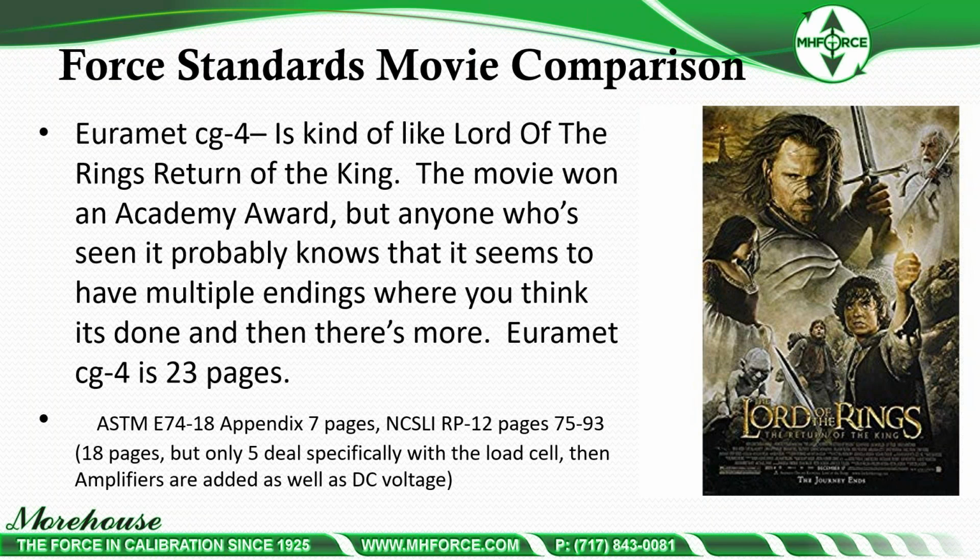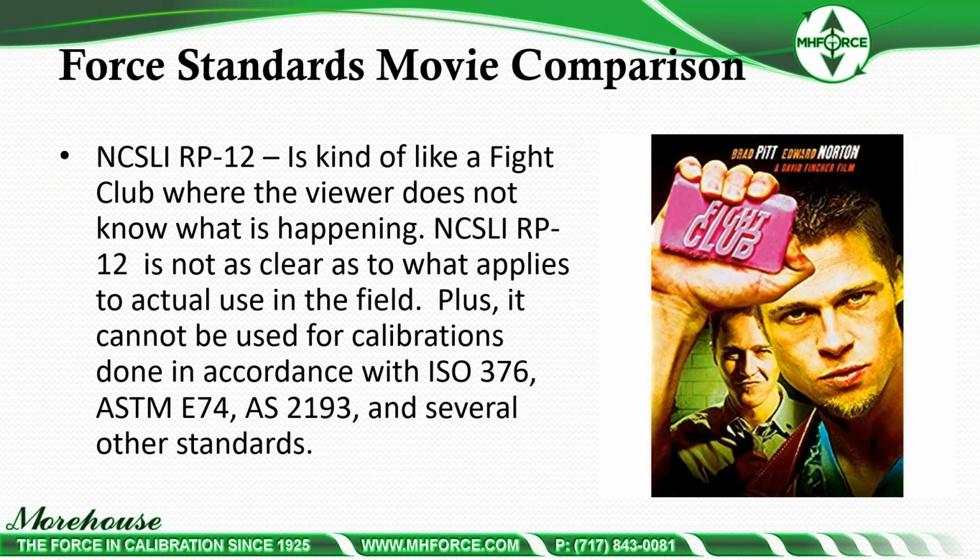We compare that with the other ones I discussed. The ASTM E74 appendix is 7 pages. NCSLI RP12 is 18 pages, but only 5 specifically deal with the load cell. Then amplifiers are added as well as DC voltage. And we have NCSLI RP12.